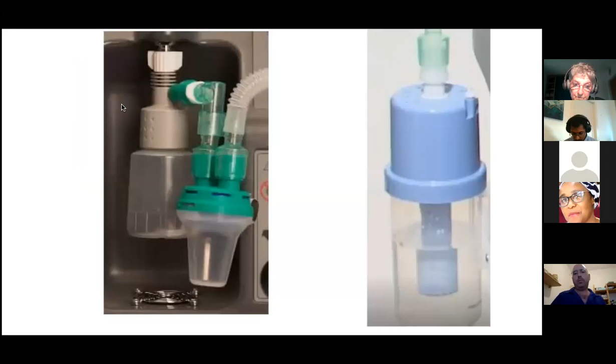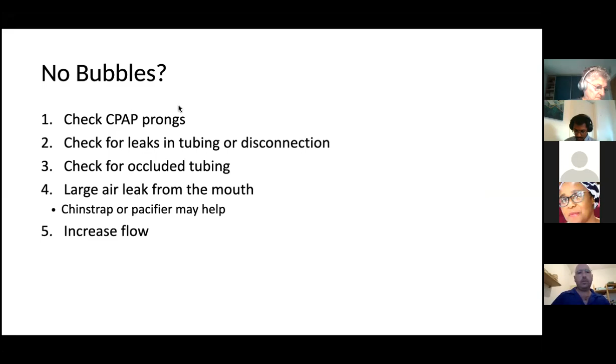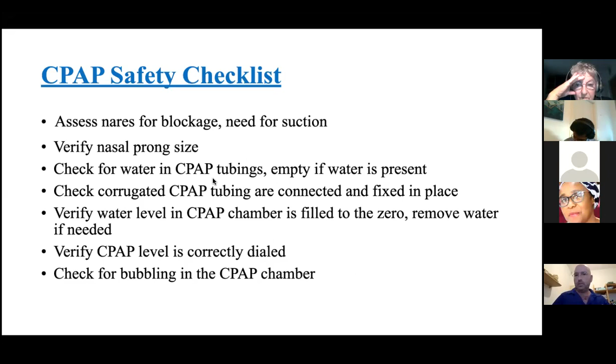If there are no bubbles, we need to check if the prongs are okay, if there's no kink or if it's not torn. Same goes for the tubes. And if everything is connected properly, you can try and increase the flow and see if it's working. Another important point before we connect the prongs to the patient is to check that there is no excess water inside the tubes, because if we cleaned the tubes and didn't dry them properly, some water can still be left in the tubes. And if we connect the baby to the prongs, the water can flow into his nose and obstruct it and can interfere with his airway.